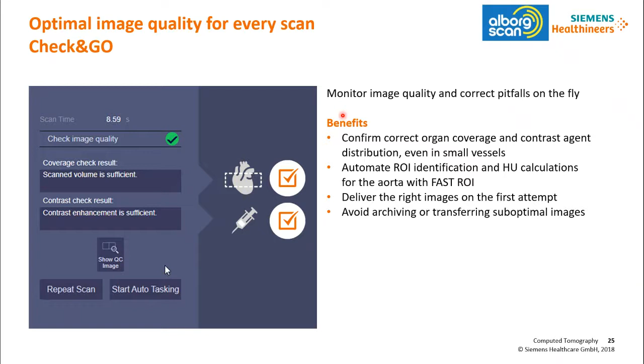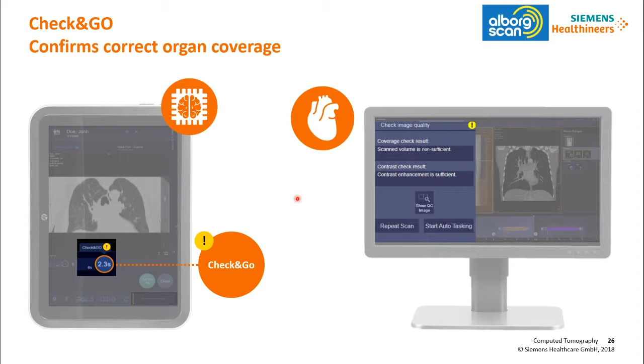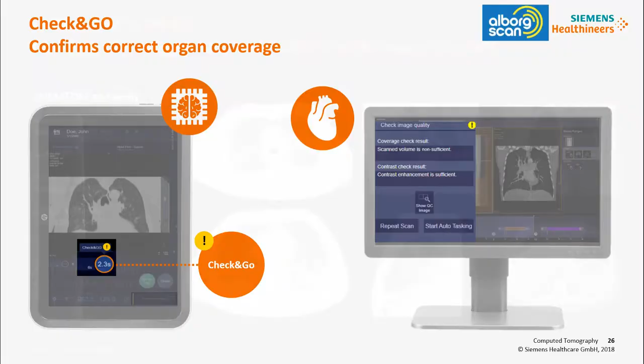Suppose in the scan, if you see here, you just cut the costophrenic angle, or just the bottom of the lung is maybe one or two slices down, there may be a pleural effusion, but you cut it in that scan. The system will automatically check this and tell you your coverage is wrong. Do you want to repeat the scan? Either you can repeat only that area and cover the full lung, or in the same way, you have done an angio and the contrast is not reaching that area, and then you can immediately repeat that scan. So maybe an extravasation or some mistake, so the vessel is not filled with contrast, then you can immediately repeat the scan. This way, the system will always check the quality of the image and will intimate you: do you want to do it the proper way or continue the way you have done? So it will always intimate you.